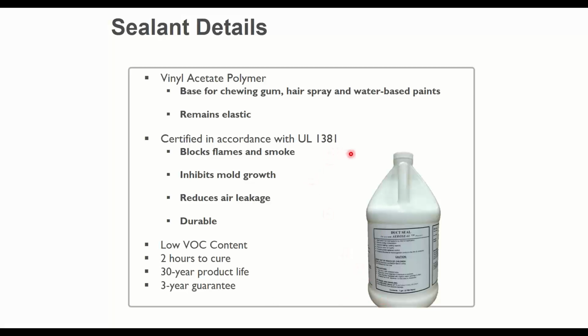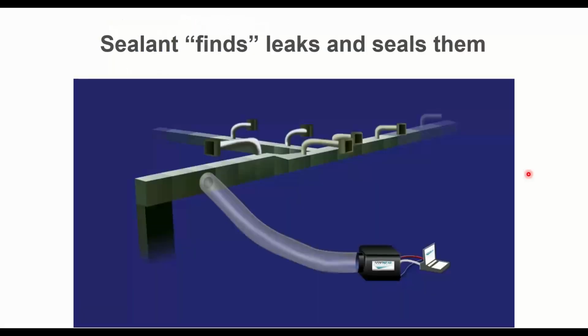It has UL 1381 rating. That is for flame spread. So you can use it on duct material. So it is an approved material to use on HVAC duct systems.